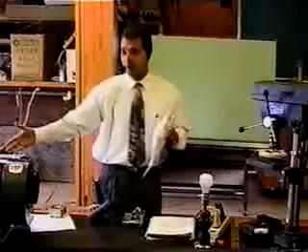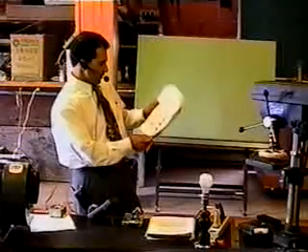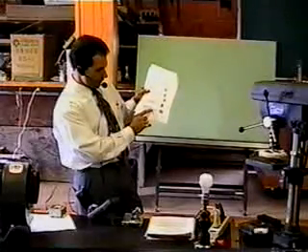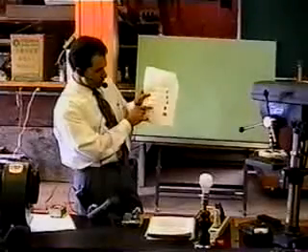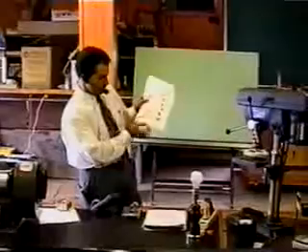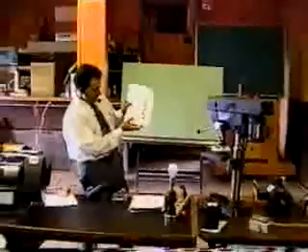From profile five you can also set different set point saving levels — four, five, and so on. I wouldn't run saving level four on that bowling alley because that's just a little bit too much. So I'd use the one that gives full power when the load changes and set point saving level five. Once you start getting to profile seven, you get smooth ramp-up engagement — that's soft start. Those are for motors with belts, taking the impact off the bearings and extending belt life. That's what you want to use for machine tools, anything with a belt and pulley.